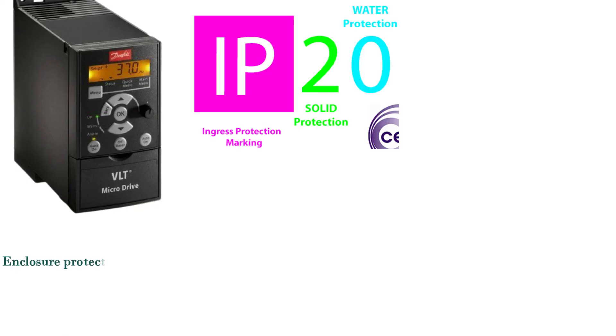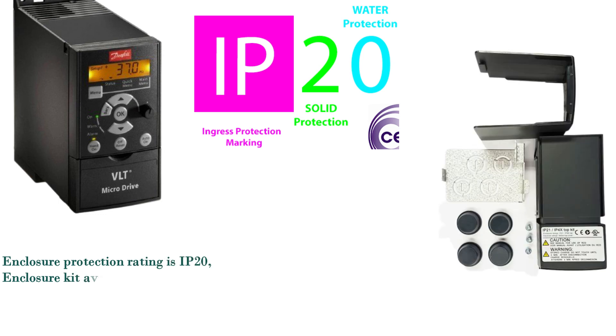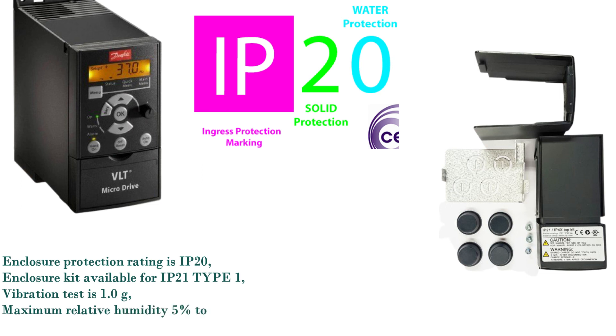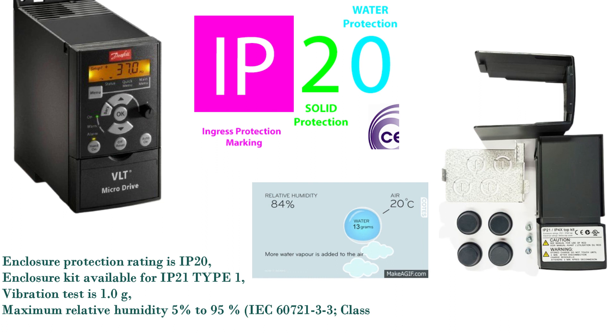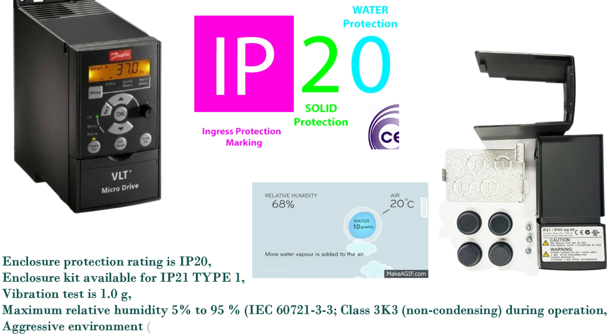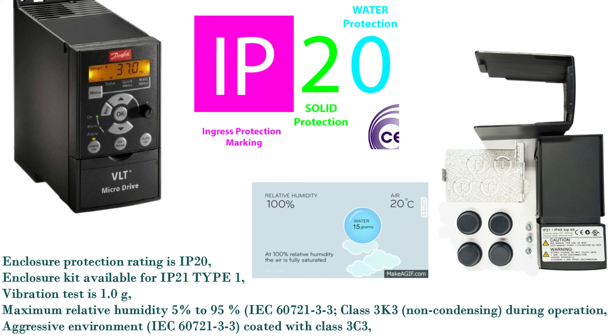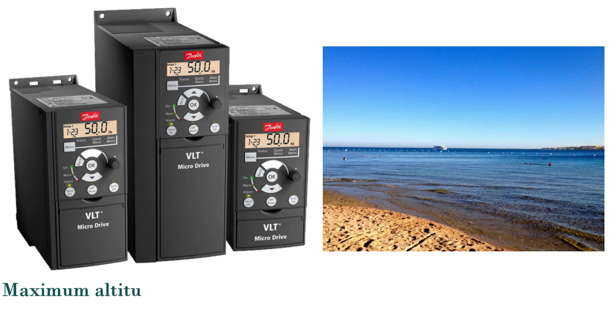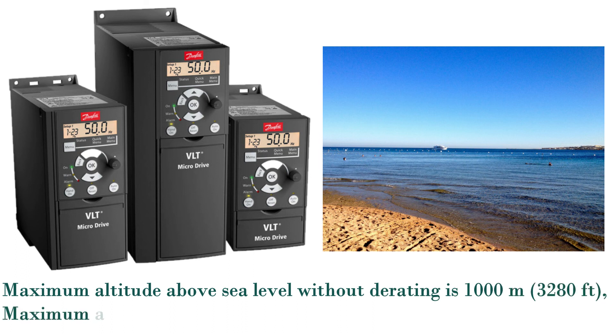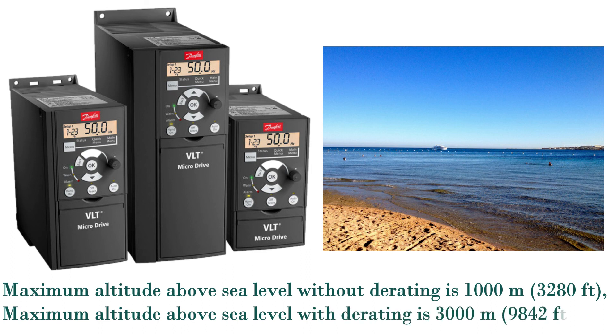Enclosure protection rating is IP20; enclosure kit available for IP21 type 1. Vibration test is 1.0 g. Maximum relative humidity 5% to 95% per IEC 60721-3-3 class 3K3, non-condensing during operation. Aggressive environment per IEC 60721-3-3 coated with class 3C3. Maximum altitude above sea level without derating is 1,000 meters (3,280 feet); with derating is 3,000 meters (9,842 feet).